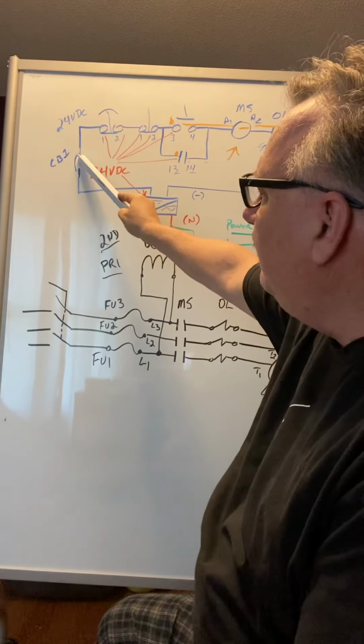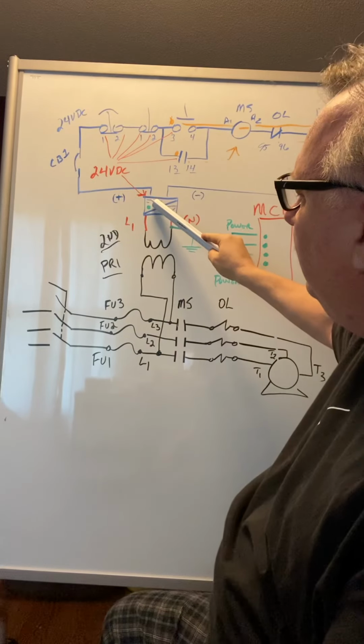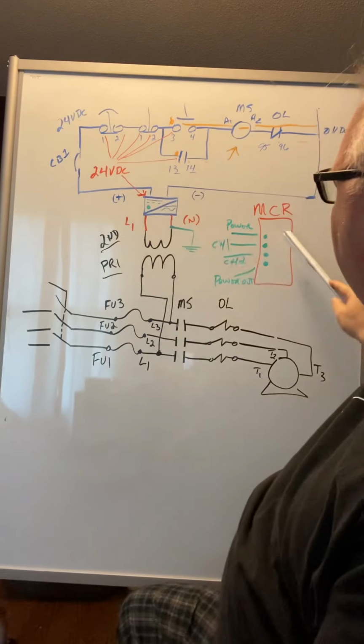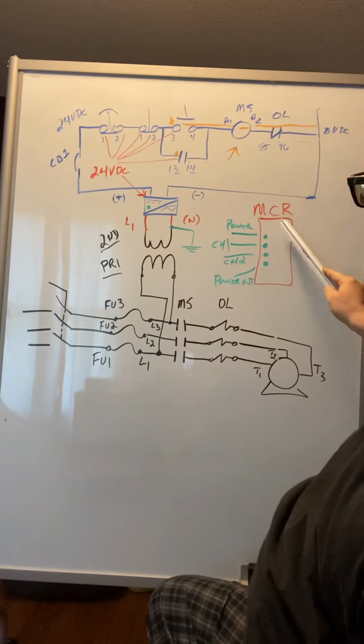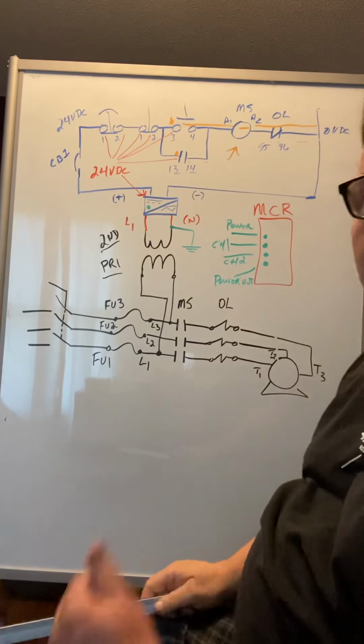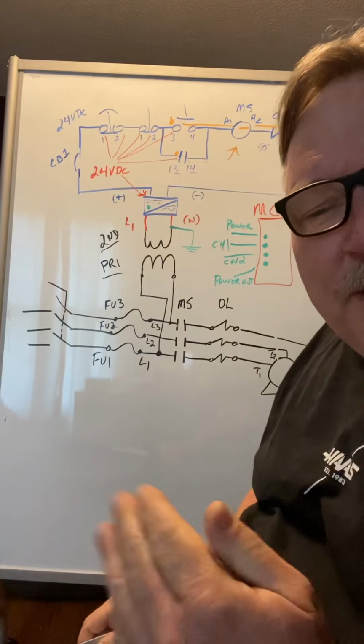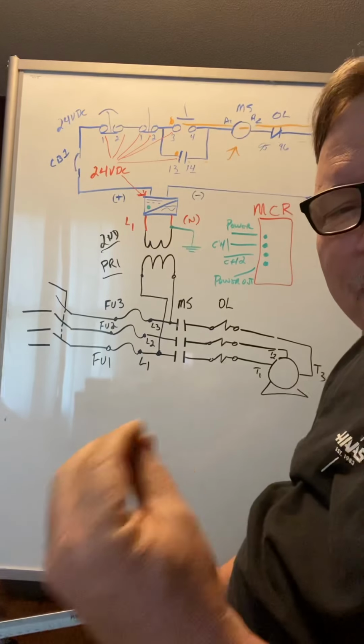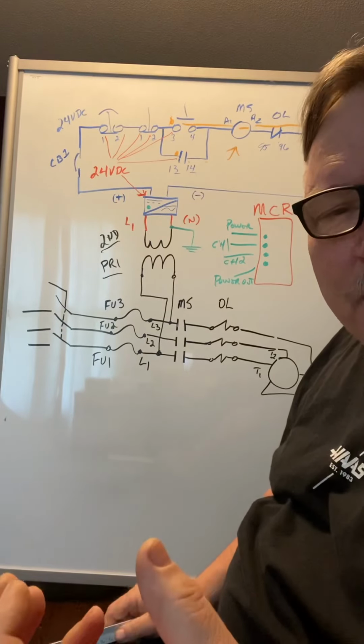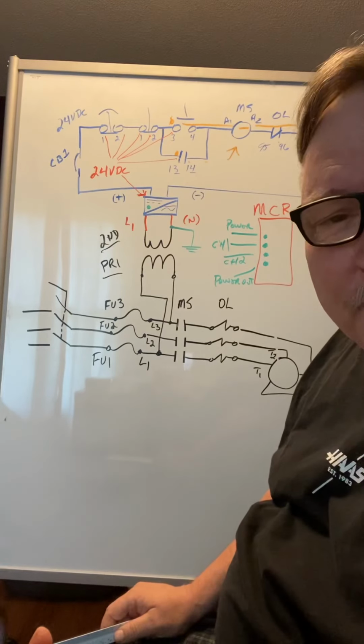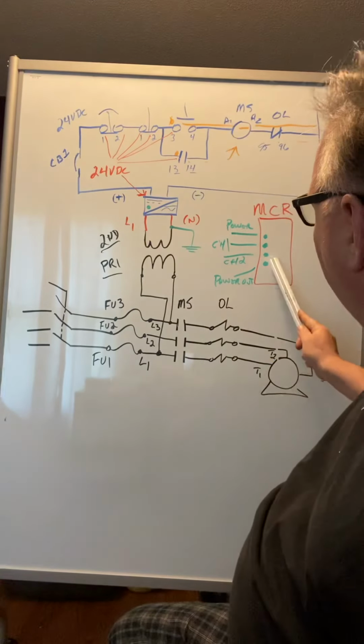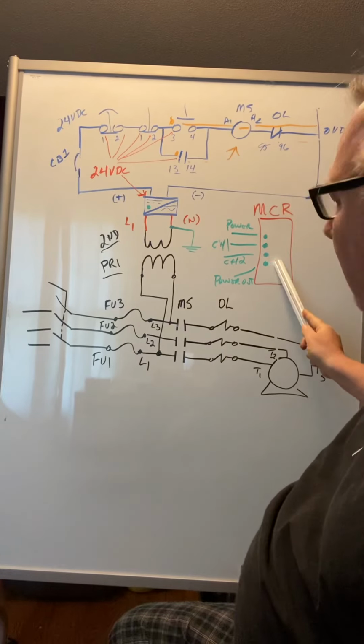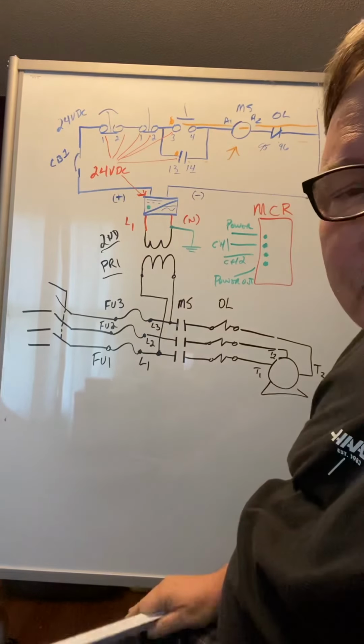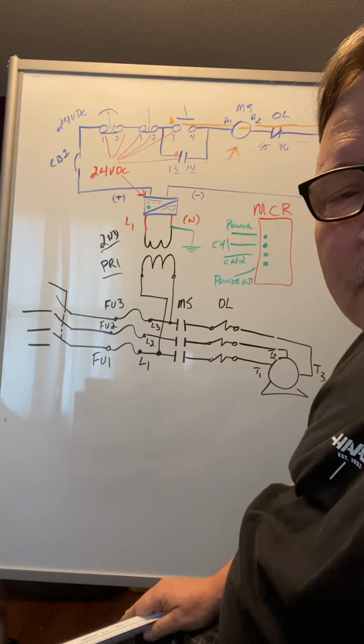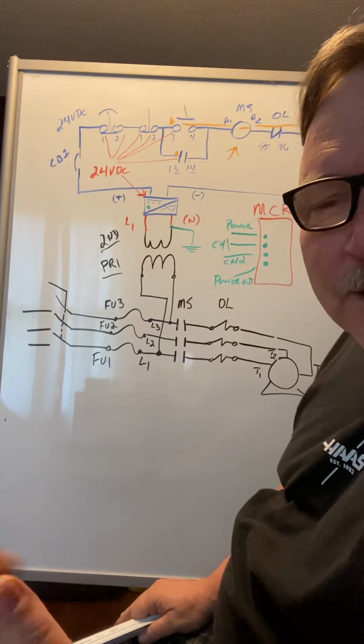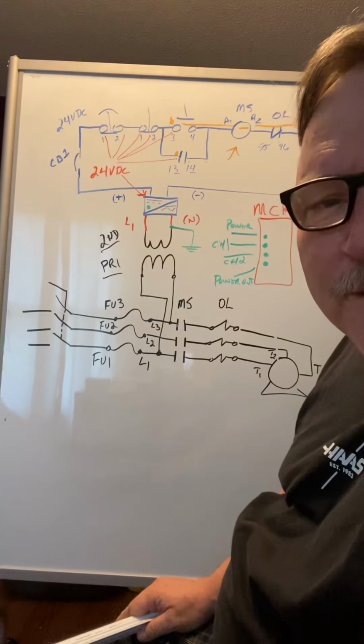Make sure that circuit breaker that's right there isn't tripped. Make sure you have your green status light on your power supply, on your master control relay or your safety relay. Make sure you got all your green lights. Four is typically what you're going to see, but some have less, some have 3, some have more. But bottom line, if there's an LED in that master control relay, that should be lit. If it's not, tell your operator to start checking safety devices, because if this bottom light is not on, and if any of these are off, that bottom light won't be on. Don't waste your time with your meter looking at anything else until you check all your door interlocks and safety devices and presence mats and light curtains and all that kind of stuff there. Okay?